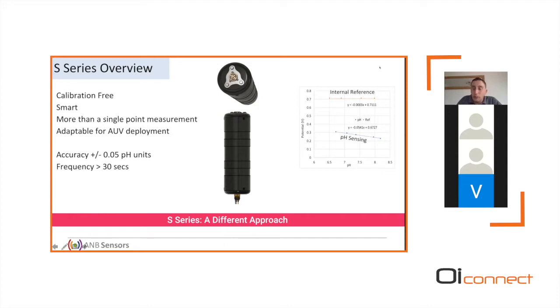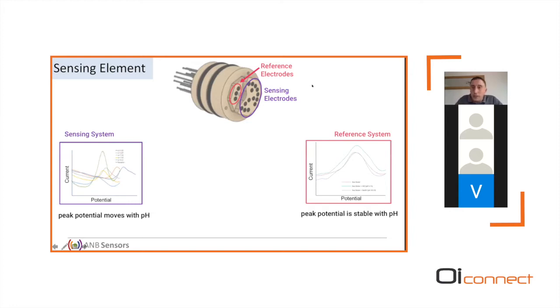How does it work? I'll move on to that in this slide. On the surface of a sensor, we have an array of electrodes. We have a conventional reference electrode, which is the grey dot, which is masked underneath here. We have a series of reference electrodes, and we have a series of sensing electrodes. Our sensing electrodes use electrochemistry which has redox potentials which are sensitive to the pH of the solution in which they're immersed. That is to say, this peak potential here is a signal to the pH of the solution. Our reference electrodes don't have that, so they're actually pH inert. This potential here purely tells us about the reference electrode potential of our conventional electrochemical system.